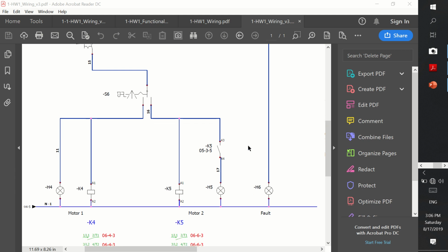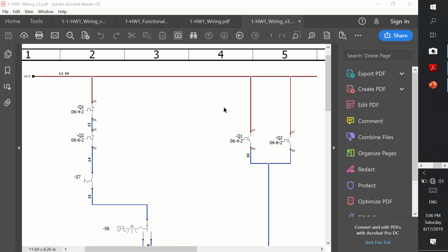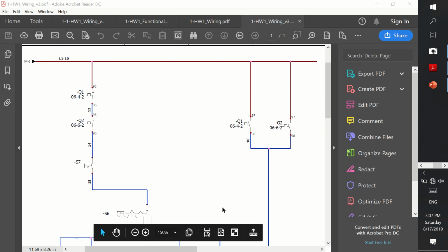So, one other issue, hopefully you have noticed in the video in part 1: once I tested the fault condition, I started the second motor. However, when I tested the overload condition, I just pulled the trip or the trigger of the first contactor, even though it was not running. And this is because of the OR function shown here in the RLC diagram.